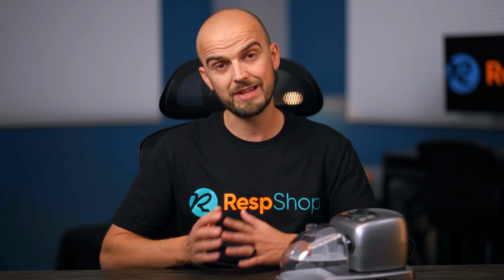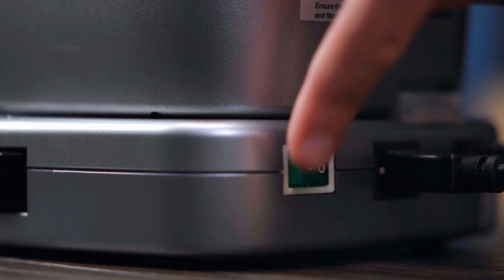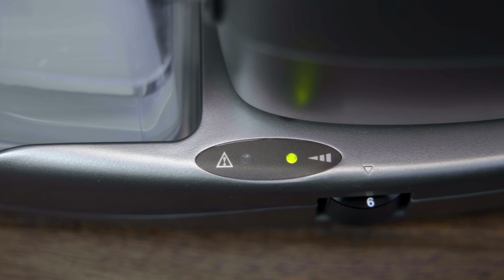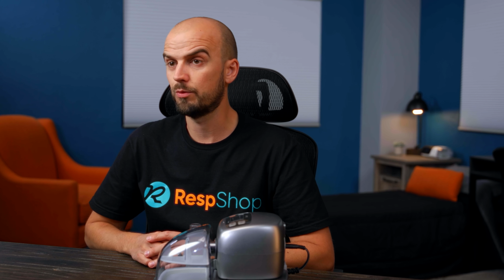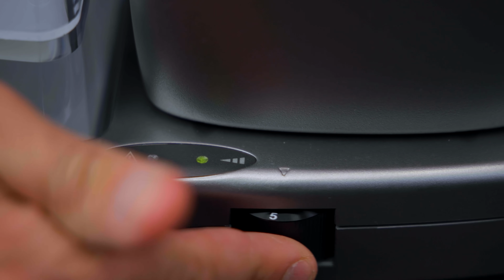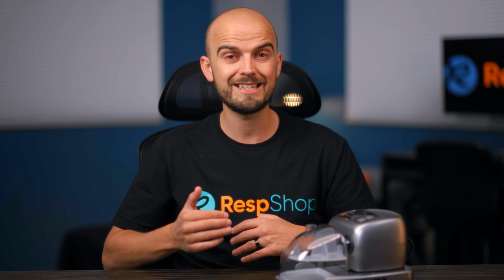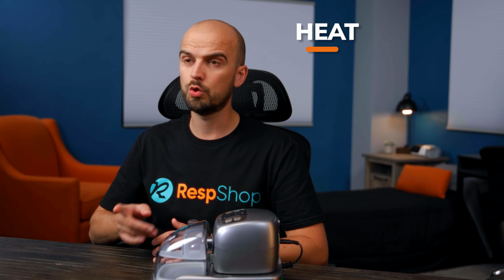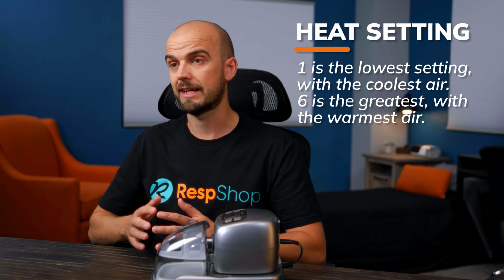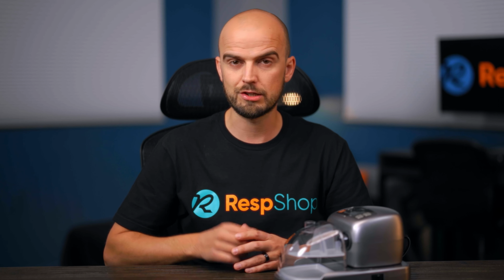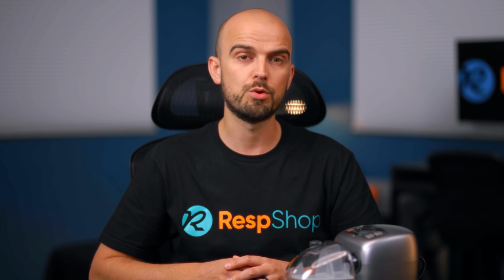When the unit is used with the heater platform, the screen will not light up with standby unless the platform is switched on using the green switch at the back. This switch will also turn on the heater plate to warm the water in the humidifier. A green light will turn on at the side of the unit to indicate that the heater plate is warming the water. Below the indicating light, there is a rotation knob with 6 settings. This controls the heat of the water as well as the humidity it will supply to the passing air. 1 is the coolest air with the least humidity, while 6 is the greatest. You can adjust this setting freely to suit your needs and the environment. Note that the heater plate will turn off automatically if the water chamber is removed.